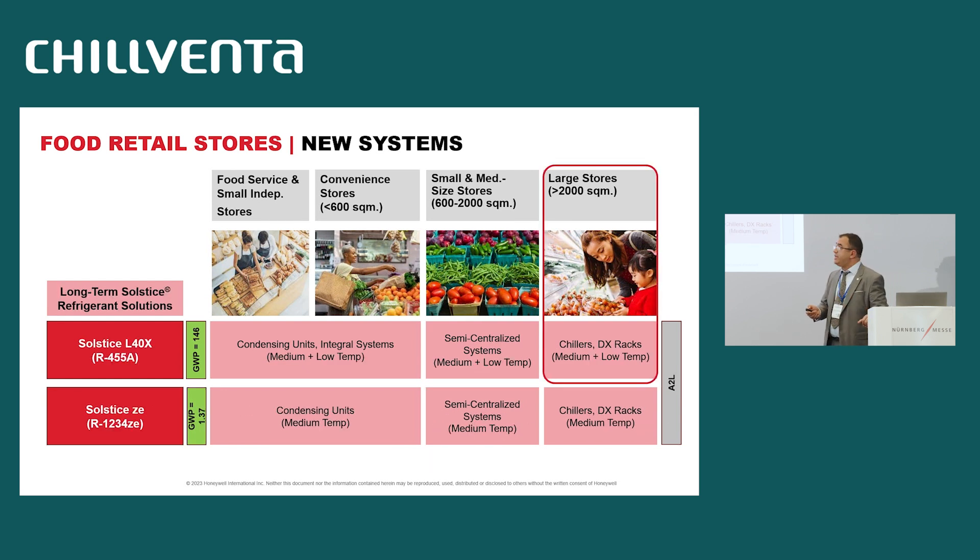For new systems, we have the same approach with two refrigerants: R455A, which is A2L with low GWP, and ze, which is ultra-low GWP at approximately 1. These solutions can be used for different types and sizes of stores. R455A with GWP less than 150 can be used both in medium and low temperature in condensing units, integral systems, semi-centralized systems, chillers, and direct expansion. For ze, it is only applied for medium temperature and can be used for condensing units, semi-centralized systems, and chillers.